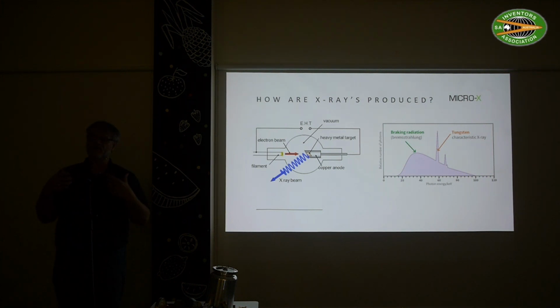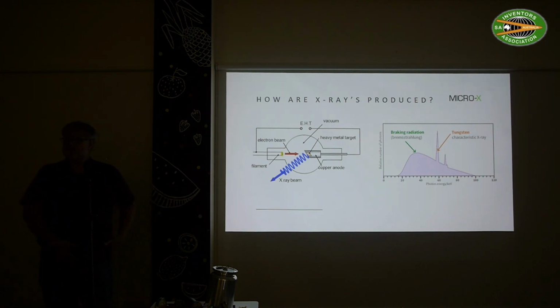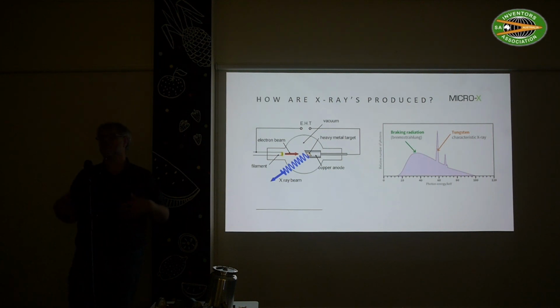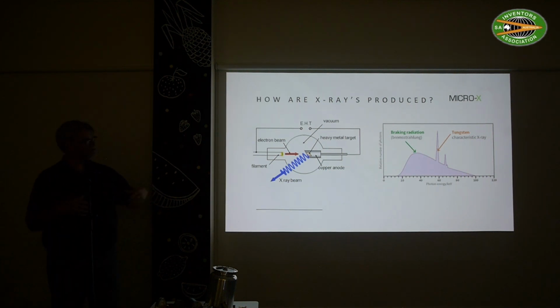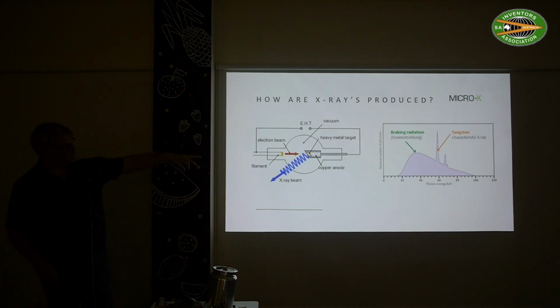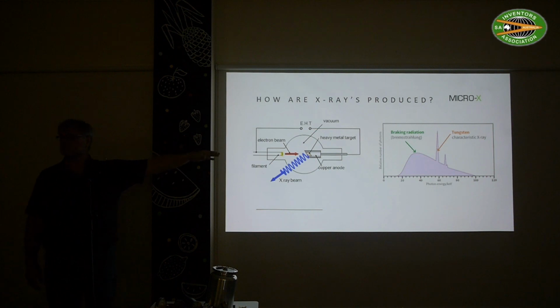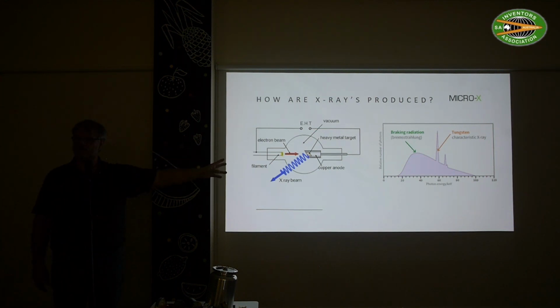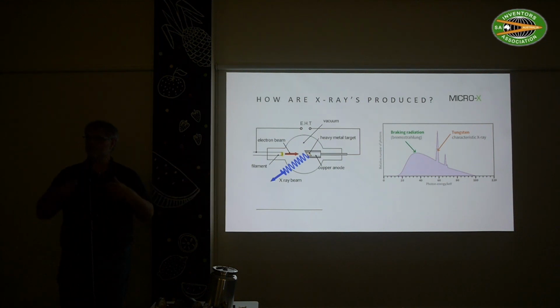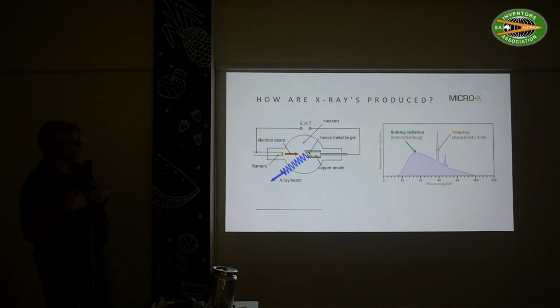And that's what you find in regulations, that for a hand, for an arm, you only need this amount of mAs. For a hip, which is bigger, you need this amount of mAs. And there are different energy levels, and some filtering happens on the energy levels, because the one at 40, where the big peak is, typically is not very useful, so they tend to filter that out and use some higher levels by putting different materials in front of the X-ray to stop it in the right way. So there's a lot going on there.